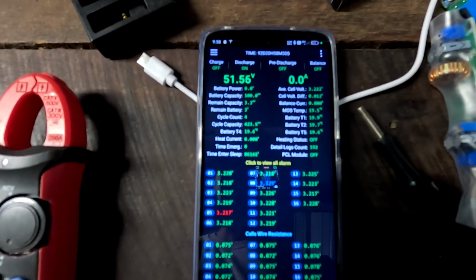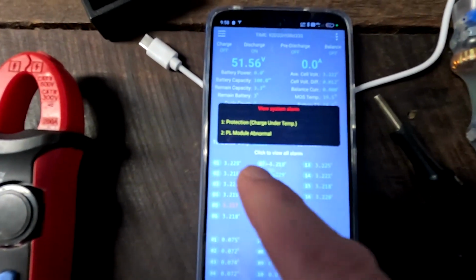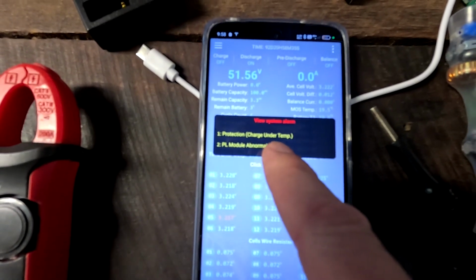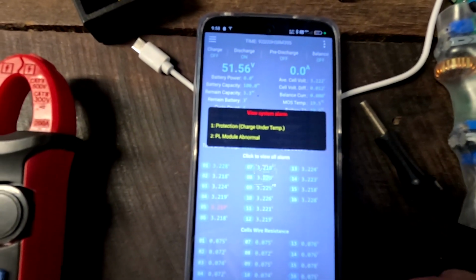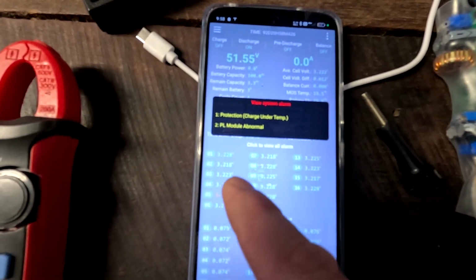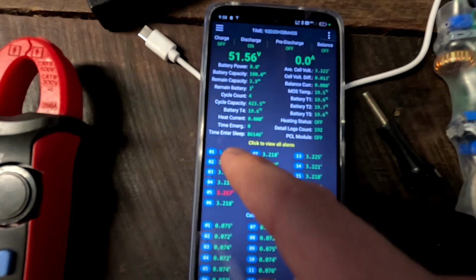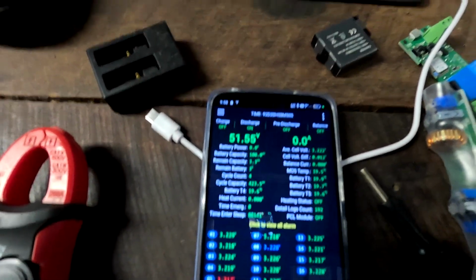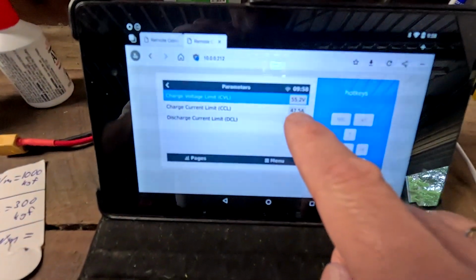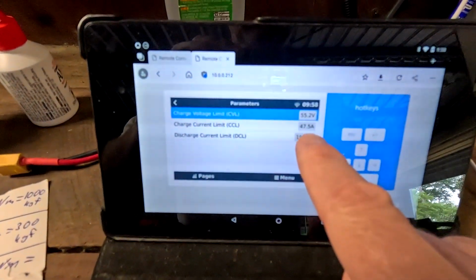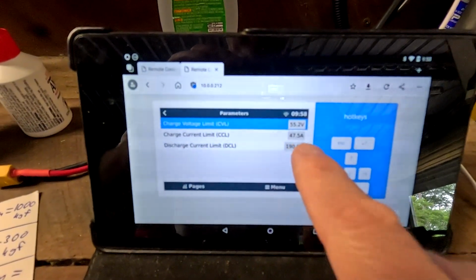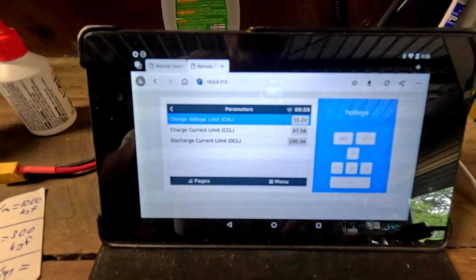That is interesting. We have a charge under temperature protection here with one of the BMSs, because I have set the temperature to 20 degrees and we are just underneath this 20 degrees. So the BMS has actually turned off the charge MOSFETs, which is correct, but it is still reporting a charge current limit of 47.5 amps to the inverter.